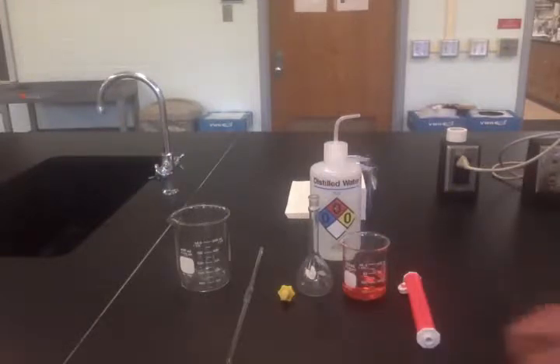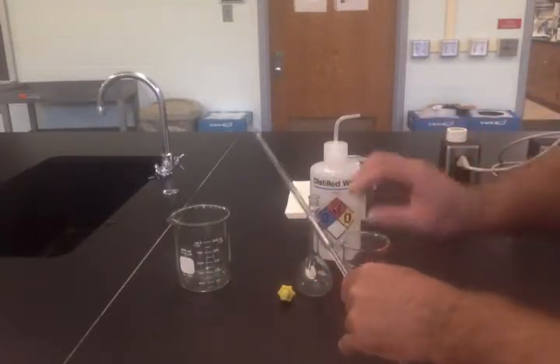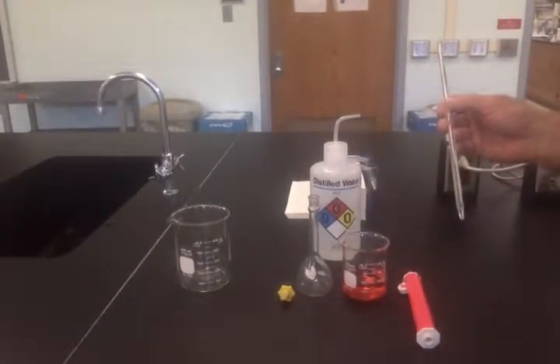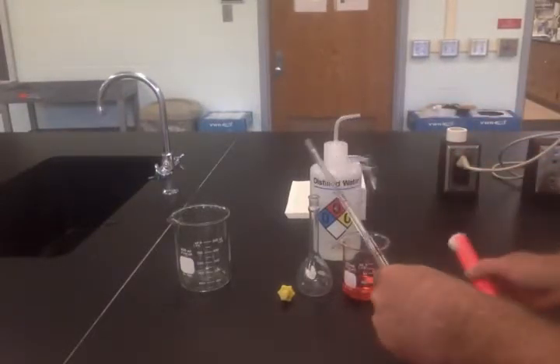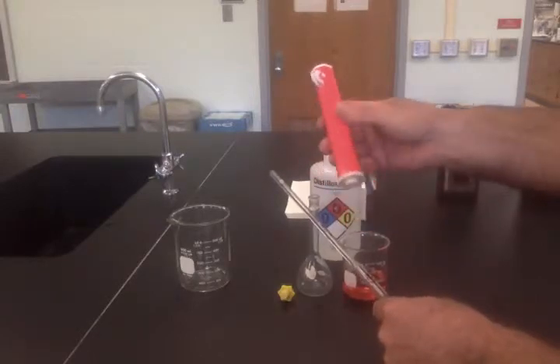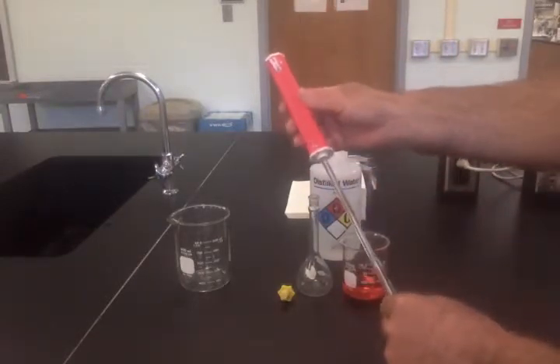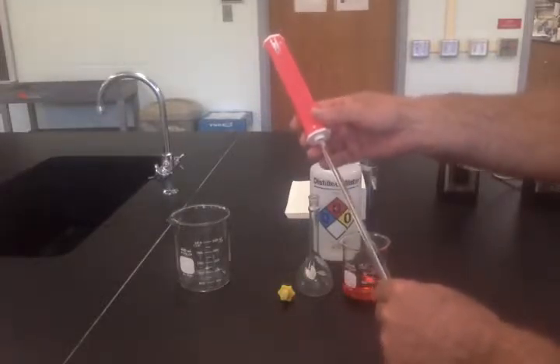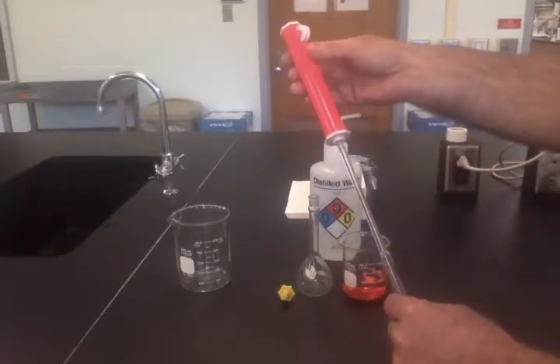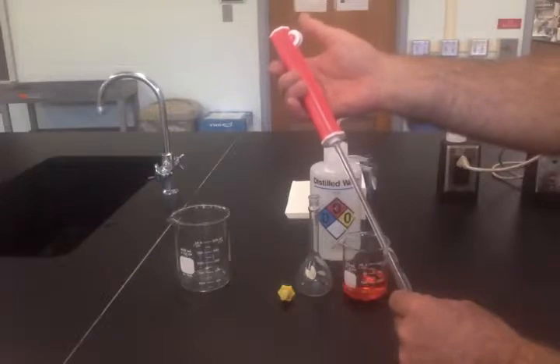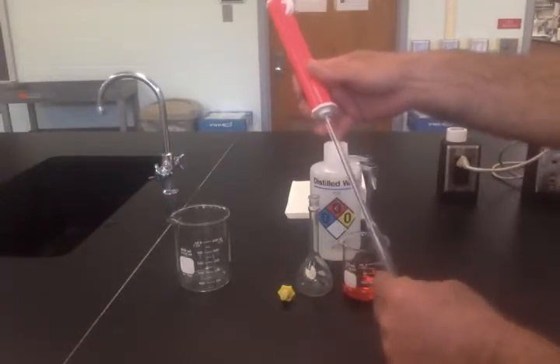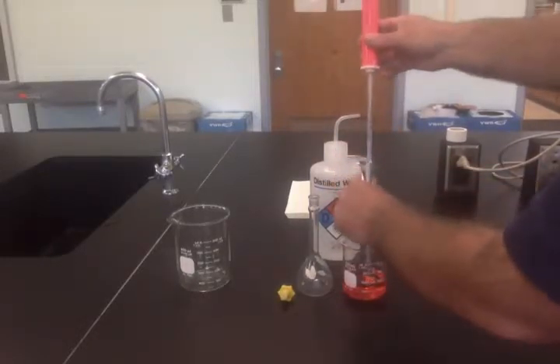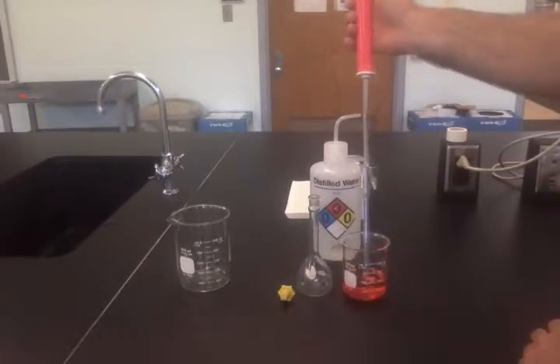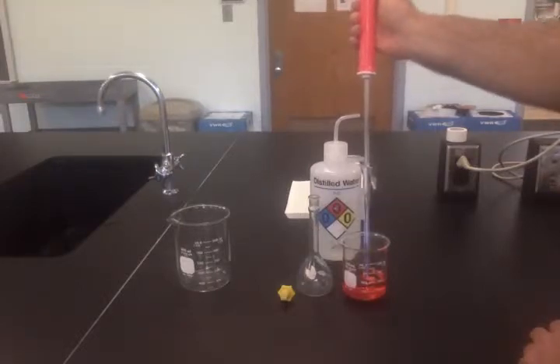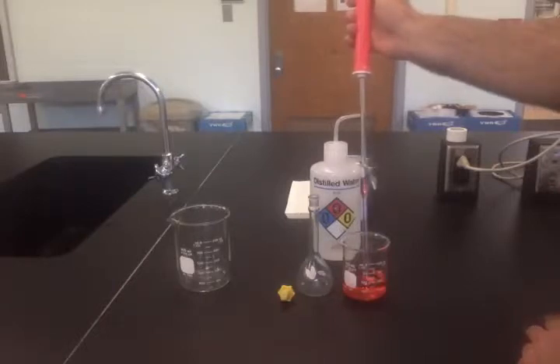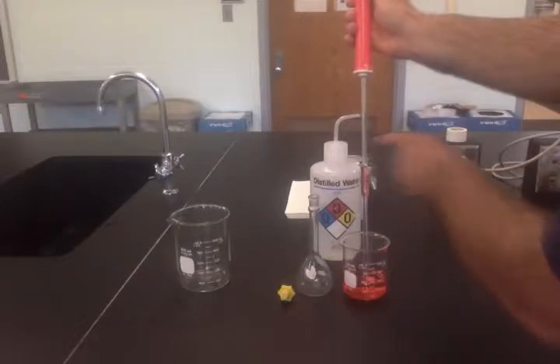So initially what you will need to do is to rinse the transfer pipette with the solution that you are going to start with. To do that, you're going to take your transfer pipette and insert it in the bottom of the pipette pump, and this doesn't have to be inserted too hard, and the pump will have a wheel that will allow you to take a plunger and suck solution up into the pipette. Place the pipette down into the concentrated solution, and using the wheel, draw solution up into the pipette. You should draw a solution such that the level of the meniscus goes above the calibration mark.